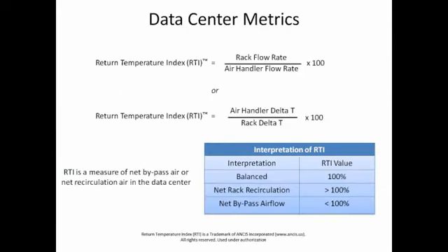So the other metrics we're going to use are RTI and RCI. RTI, we're going to use here as a ratio of the rack flow rate to the air handler flow rate. You want these matched as closely as you can get them as well. In other words, if you can predict what the racks are going to require, then you can get the air handler to give you just what those racks require, then you've got a perfect situation. You've got a ratio of 1, and everything is balanced at 100%.